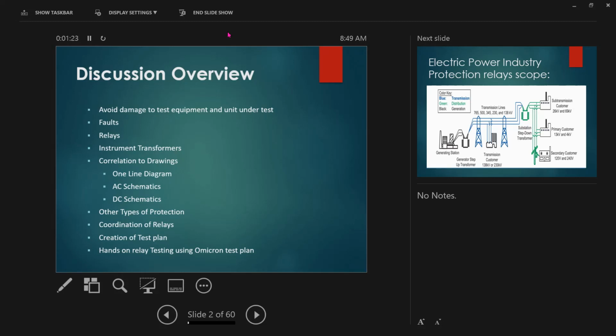So yeah, discussion overview for the relays. Of course, to avoid damage to this equipment and the unit under test. For example, if you do testing, instead of doing more harm, you need to be aware of how you do this testing, not only for the relays, for the client, but the test equipment as well. As Steve spoke to me yesterday, I think the Doble was sent to a service center. It cost him 30 grand, and they found that there's a wet spot inside. So I'm not sure how they did it on site. But if we don't have some kind of responsibility for this equipment, it costs the company more.